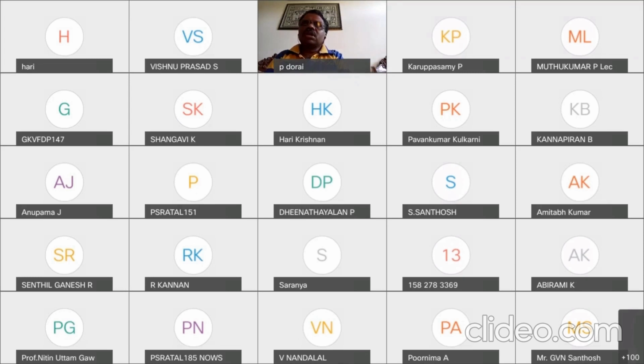And we have an electrosurgical unit. The electrosurgical unit is used for cutting and coagulation during surgery, which helps minimize blood loss during the surgery. So it has a sensor. Once we plug in all the respective sockets, with the earth pad and the active cable, there is a micro switch inside which acts as a sensor.